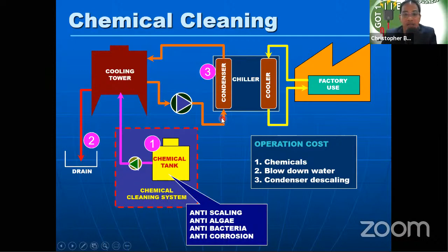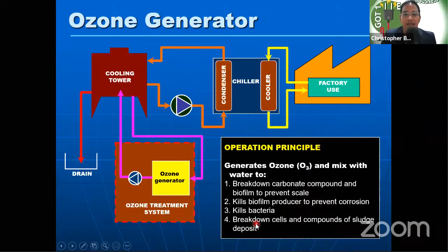So we ended up with our research, pinag-aralan ko ito ng 5 years bago namin kinonsider installing an ozone generator. So ito yung ozone treatment system namin. Instead of using chemicals, yung ozone ang ginagamit namin to mix with water to break down carbonate compounds and biofilm to prevent scale, kill biofilm producer to prevent corrosion and kill bacteria, and break down cells and compound of sludge deposit.